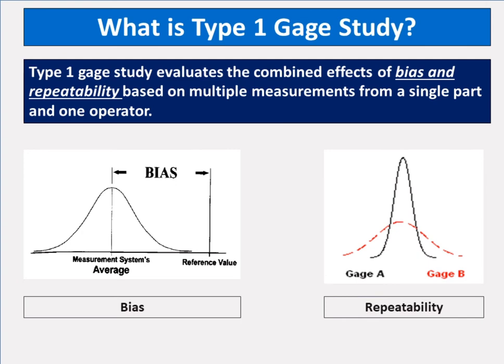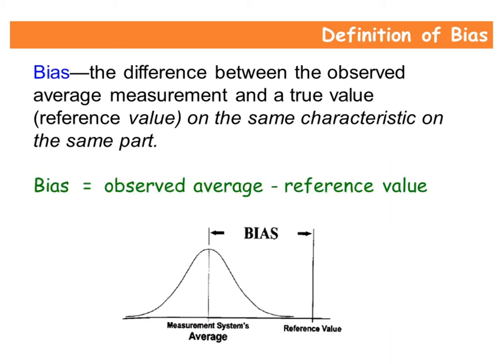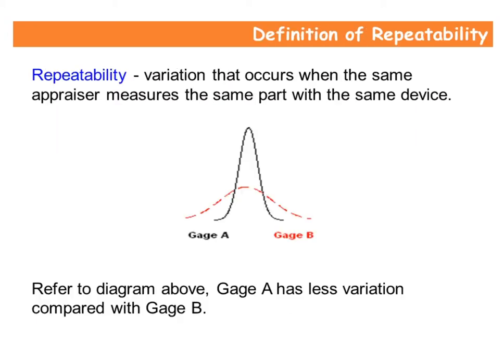Type 1 gauge study evaluates the combined effects of bias and repeatability based on multiple measurements from a single part by one operator. Bias is the difference between the observed average measurement and a true or reference value on the same characteristic on the same part. Bias equals observed average minus reference value. Repeatability is the variation that occurs when the same appraiser measures the same part with the same device.